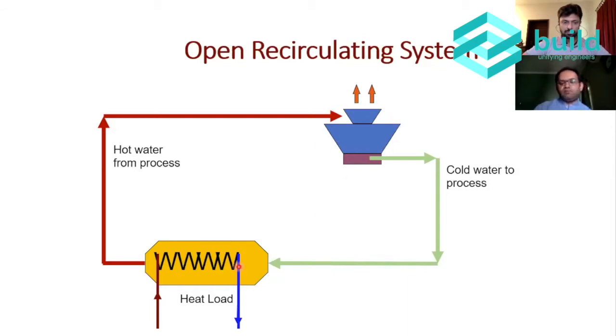So the heat exchanger can get fouled with corrosion products, scale, suspended matter, or even microbiological contamination like bacteria, fungi, SRBs, or Legionella—different types of bacteria. Since we're recirculating the water again and again, the potential for deposition and related problems increases. This arrangement, where water comes in direct contact with the atmosphere, is referred to as an open recirculating system.